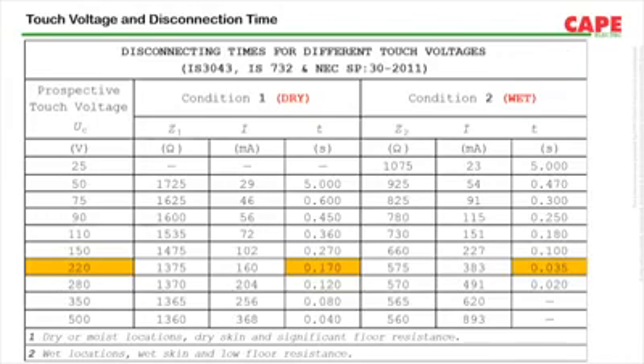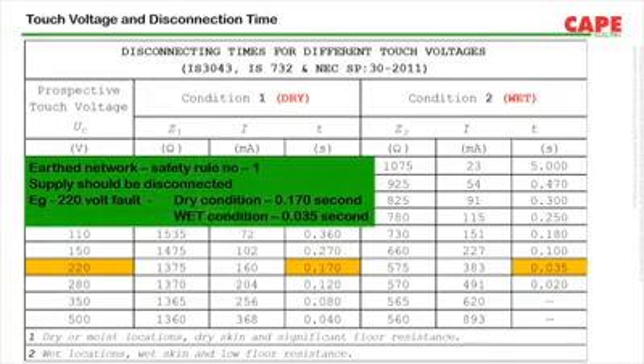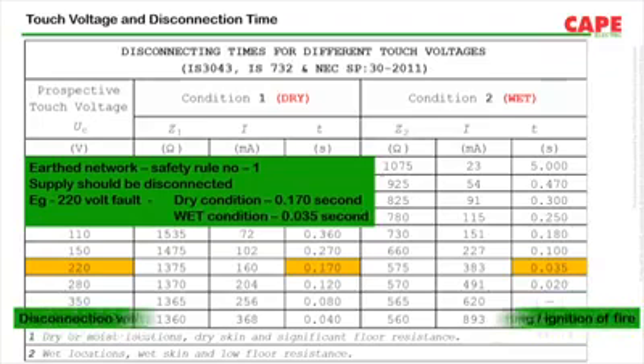IS 3043 provides a comprehensive chart on disconnection time during earth fault, applicable to dry and wet location or wet condition. Based on the fault voltage and condition of the installation, maximum allowed disconnection times are provided in the table. For example, a 220 volt fault, that means a fault of negligible impedance, in dry condition, the maximum allowed disconnection time is 0.170 second. This means the primary protective device, which is nothing but the MCB, shall trip within 170 milliseconds during a 220 volt earth fault. Disconnection of the supply within this time provides safety from electrocution and thermal effect such as fire.